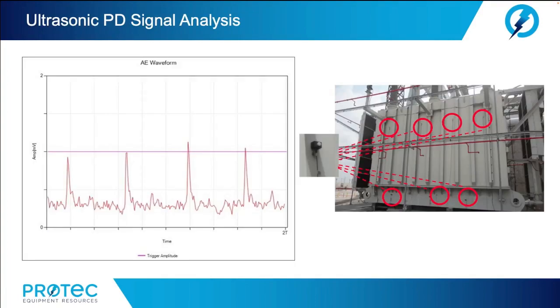All right, now let's talk about ultrasonic partial discharge signal analysis. Phase resolve techniques are also used to analyze ultrasonic PD signals. The analysis techniques are the same for both airborne and ultrasonic contact testing. There are several modes which can be used to analyze the signal. For example, waveform mode is shown here.